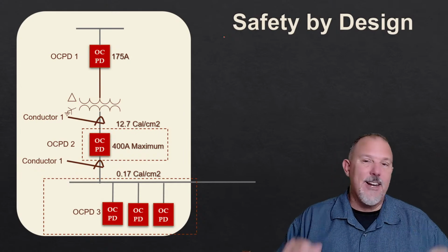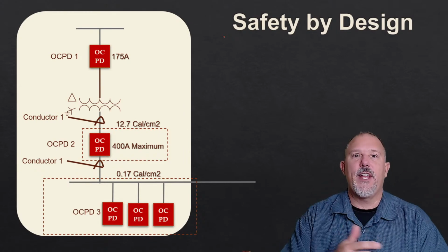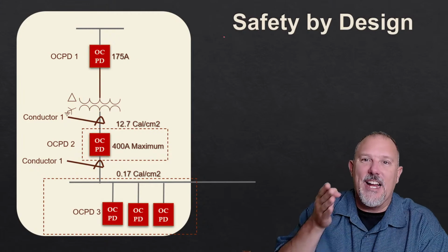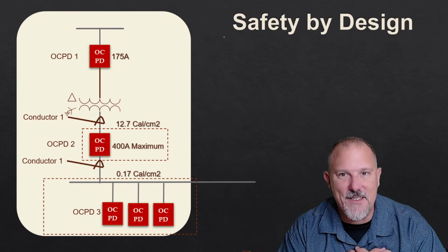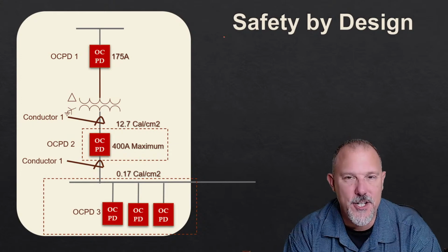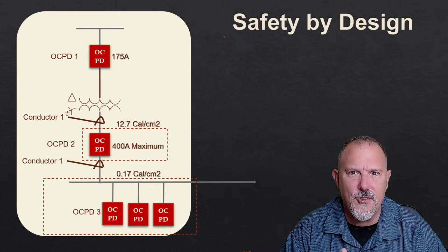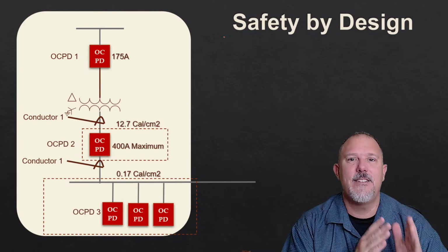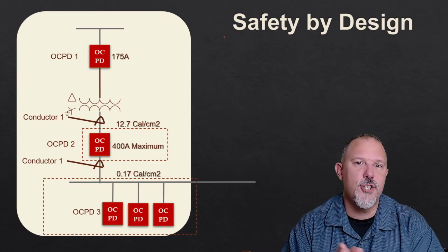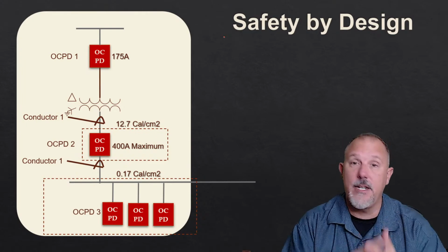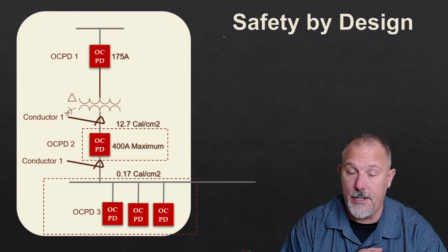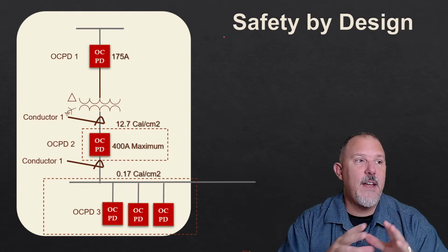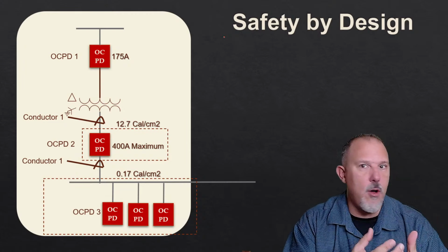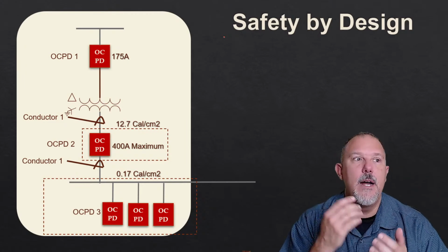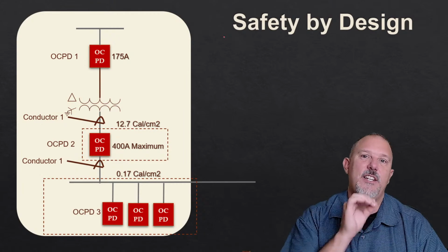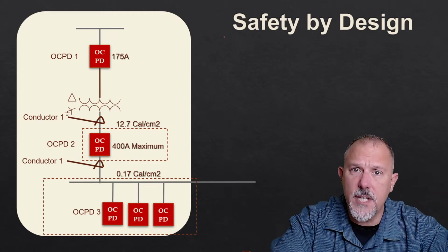So now once we did that, people were saying, look, now you can base your arc flash energy off of the main overcurrent protective device in that panel. And then the engineers were going, no, you can't do that because that line side barrier is just for shock protection, not arc flash protection. Now, it does reduce the likelihood. Think about it. If I have exposed conductors and I barrier them all off, I wrap those puppies, I have a much less chance of causing an arc flash.